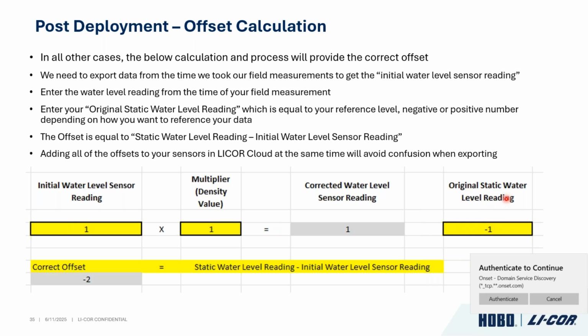And again, it could be from the top of the casing. It can be from the bottom of the well as a positive number. This is your static reading, almost your reference measurement. And so this equation right here will provide you your corrected offset. So it's your static water level reading, this right here, minus your initial water level sensor reading. Really, it's getting out that initial sensor reading and then providing you a corrected offset that you can then put into your offset configuration. I mentioned it, and I'll mention it again, do all these at the same time. Typically, you're going to come up with your offset. You're going to have all your wells or all your different locations laid out with your different measurements that you took and the time intervals in Excel. At that point, you can add your corrected offset right to that Excel file so that you can dump all these in at one time.